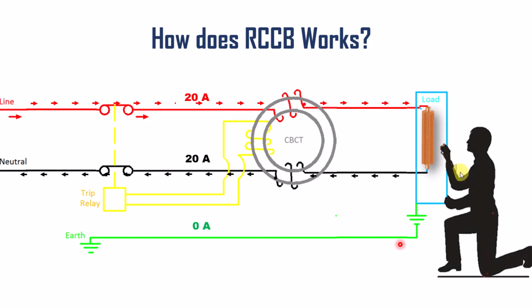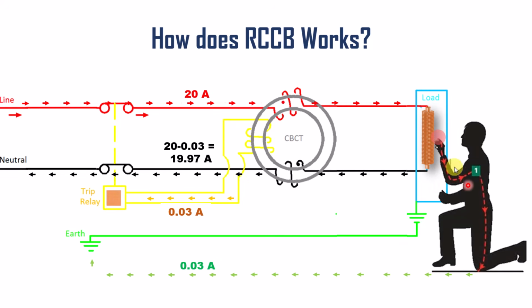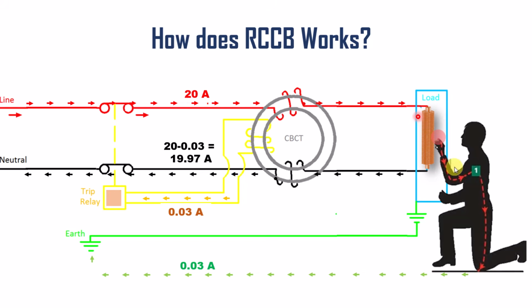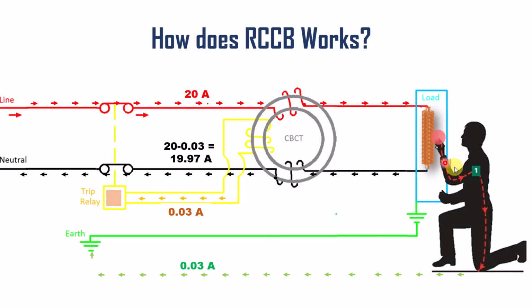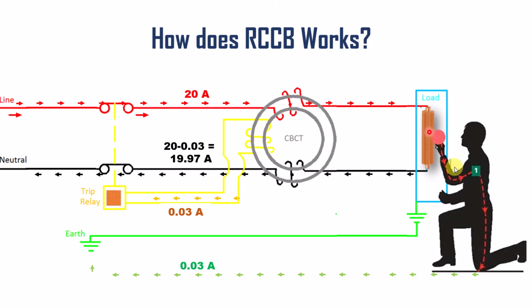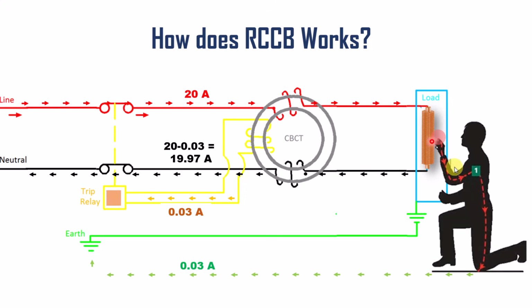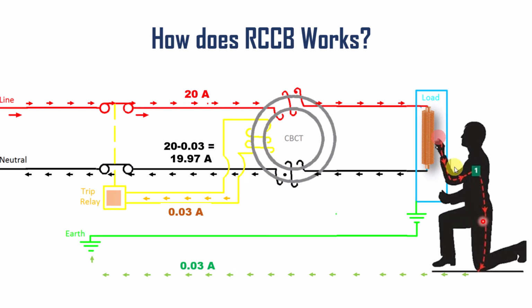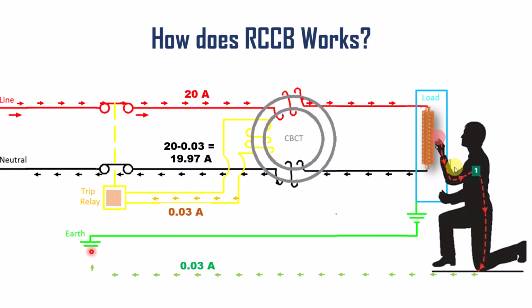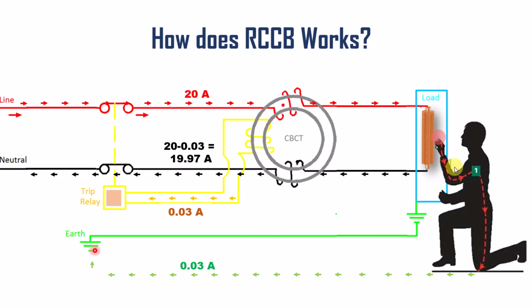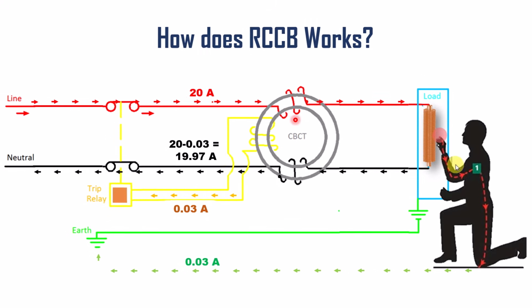Now let's see what happens when a person accidentally touches the phase or the live conductor. Here you can see as it touches the phase conductor, the current starts to flow into the body. And because of the resistance of the body, you can see that some current starts to flow through the human body into the earth, and through the earth back into the neutral of the source, which is normally the transformer. Now let's see what happens inside the RCCB.